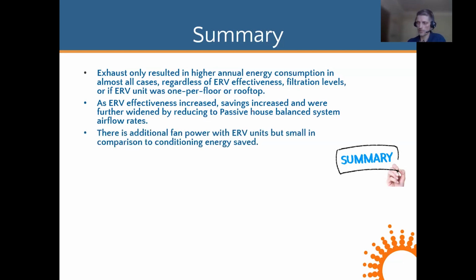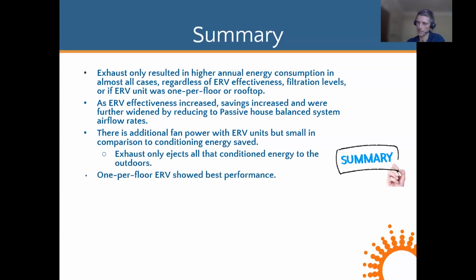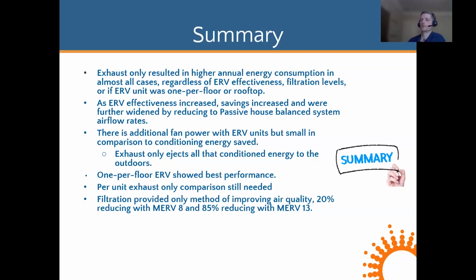There is an additional fan power with ERV units, but this was small in comparison to the total conditioning energy saved. Exhaust-only scenario ejects all that conditioned energy to the outdoors. The one per floor ERV unit showed the best performance. We'd still want to analyze a per unit exhaust-only scenario for comparison there, something to add to the study.